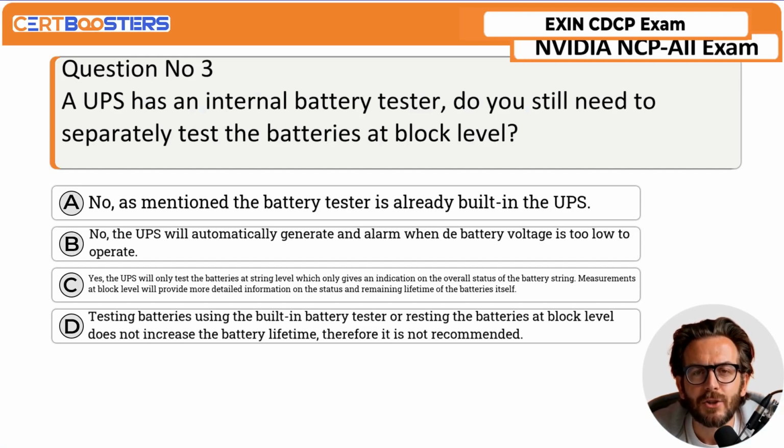Question number 3. A UPS has an internal battery tester. Do you still need to separately test the batteries at block level? A. No. As mentioned, the battery tester is already built in the UPS. B. No. The UPS will automatically generate an alarm when the battery voltage is too low to operate. C. Yes. The UPS will only test the batteries at string level, which only gives an indication on the overall status of the battery string. Measurements at block level will provide more detailed information on the status and remaining lifetime of the batteries itself. D. Testing batteries using the built-in battery tester or testing the batteries at block level does not increase the battery lifetime, therefore it is not recommended.